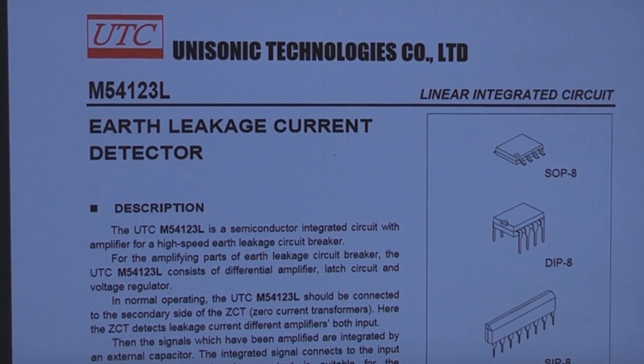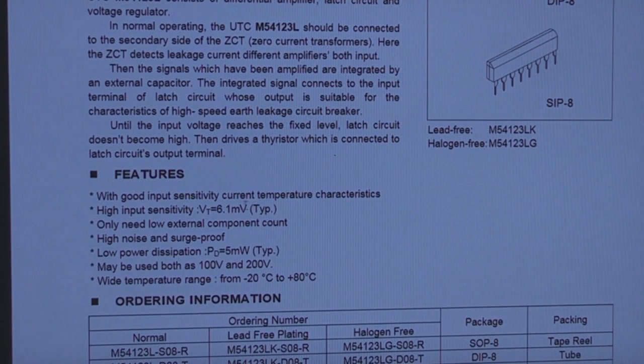Now this is the chip that's used in the RCD section. Now some RCDs are actually completely electromechanical, but nowadays, as with most things, it's generally easier to do stuff electronically. So this is a dedicated chip for that function. Interestingly, because obviously you're detecting quite a small current through that transformer, it's actually got quite high sensitivity. It's got a threshold of about 6 millivolts.